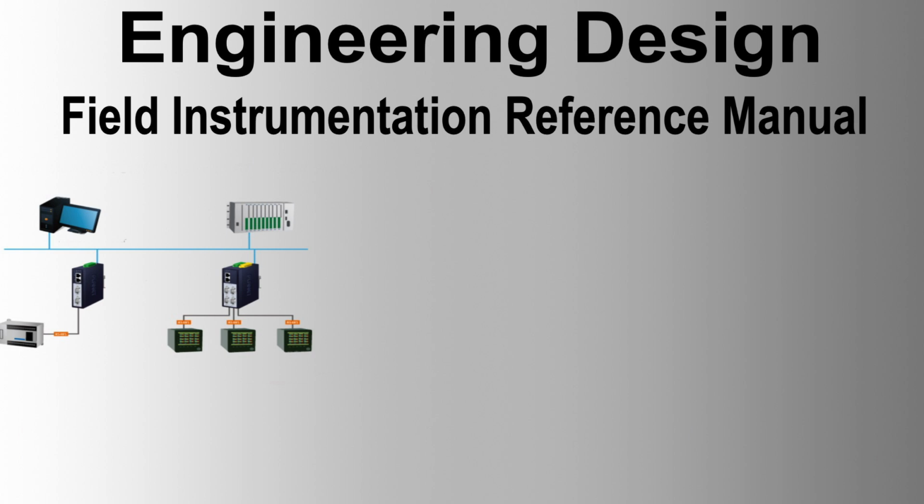Ultrasonic flow meters. Ultrasonic flow meters use sound waves to measure the flow rate of a fluid. There are two main types, transit time and Doppler. Transit time meters measure the time difference between ultrasonic pulses transmitted with and against the flow, suitable for clean fluids. Doppler meters measure the frequency shift of an ultrasonic signal reflected by particles or bubbles in the fluid, suitable for dirty or aerated fluids.